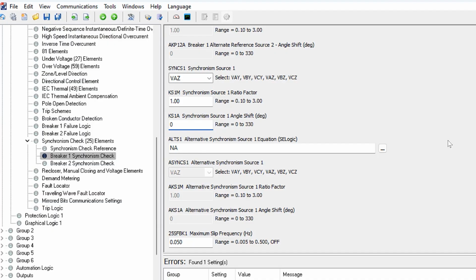Now, like I said, in our case, because we're using the A phase from both the line side and the bus side, we can just simply leave the ratio factor, which is basically just the magnitude compensation, at 1, because we would expect the magnitudes to be the same on both sides since they're both phase to neutral. And the angle shift, we can also leave at 0 because we're comparing A phase to A phase. So there's no need to shift the angles of one with respect to the other. They should be in phase theoretically.